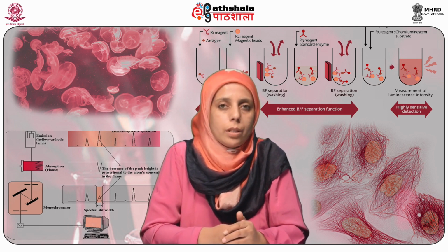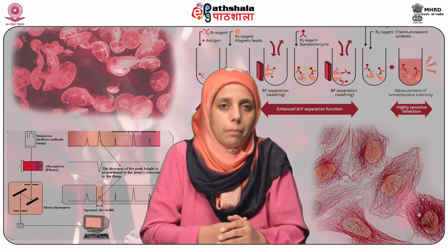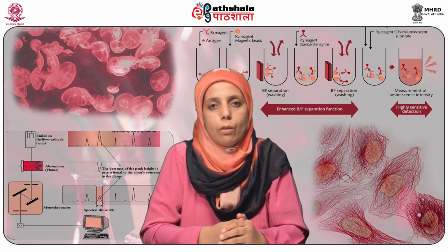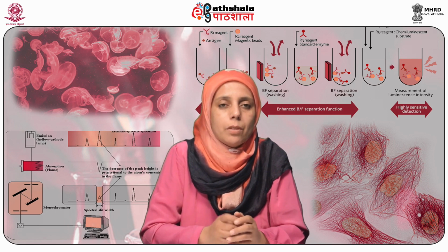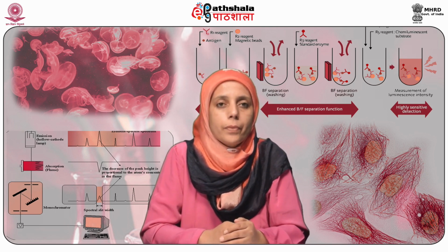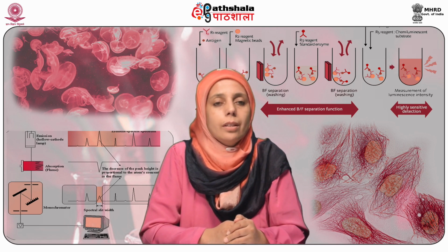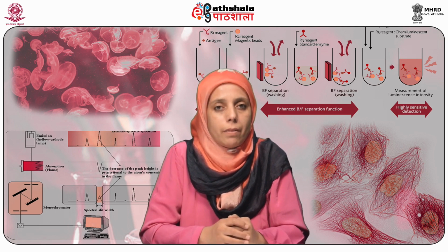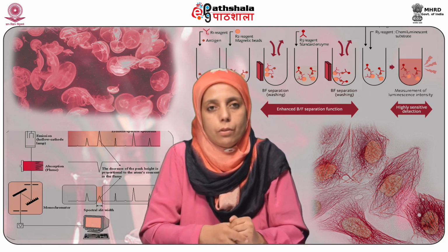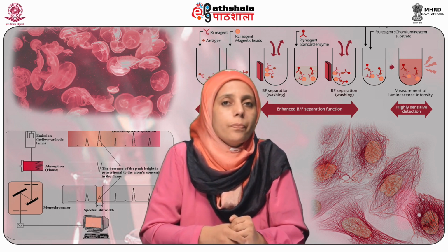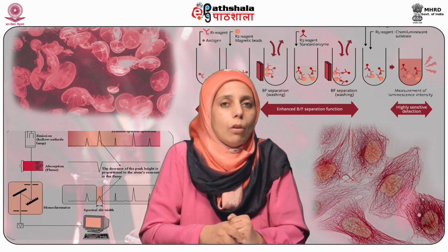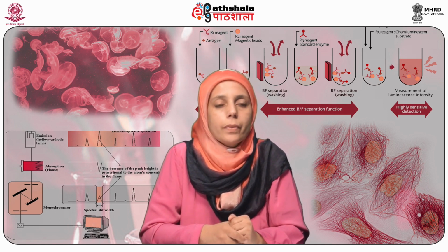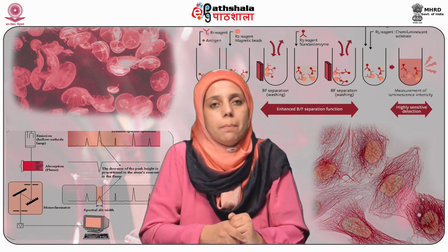Most fluorescence spectrometers use high pressure xenon arc lamp. It produces high intensity continuum light spectrum from 200 nanometers to 1000 nanometers. That means most of the visible range is covered in there. These lamps are designated according to the electrical power consumed, that means the amount of wattage used. It can be 150 watt, 450 watt or 1000 watt lamp. In instruments, 75 watt xenon arc lamp has also been used, but it's pulsed so that the peak intensity of each pulse is high.